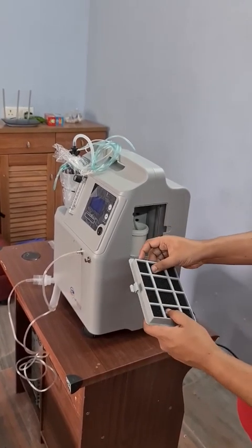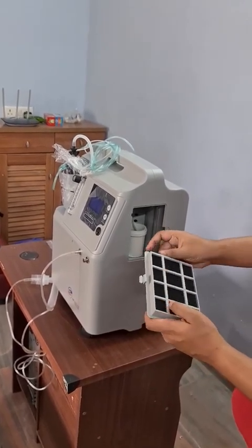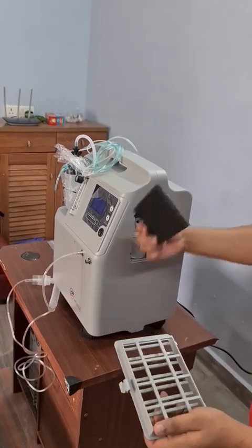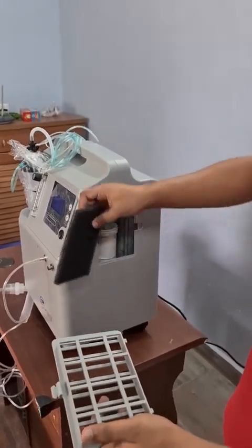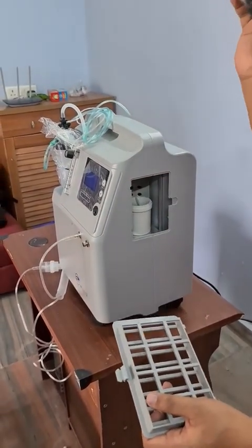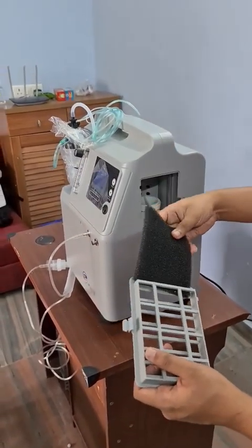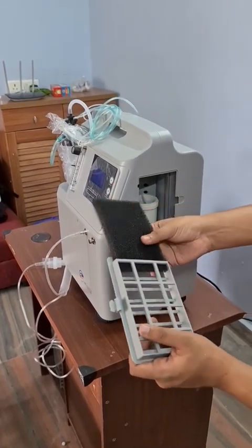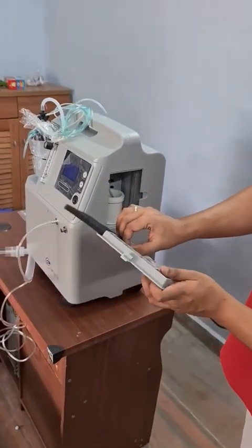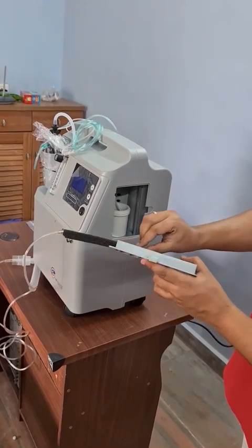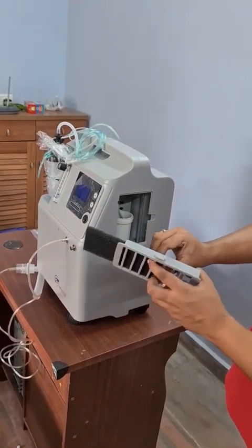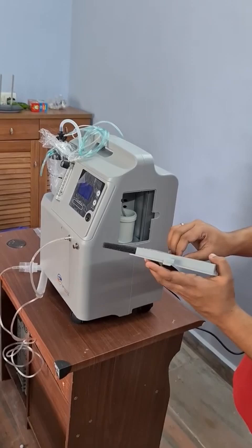So the correct procedure is to take out these filters and dust them properly. You can just tap it and remove the dust, or even if there is heavy dust, you can soak it in water, make it completely dry and then reinsert it. So cleaning the primary filter is very simple, and as a good practice, always check your filters at least once in a week. Now I am going to tell you about the secondary filter.